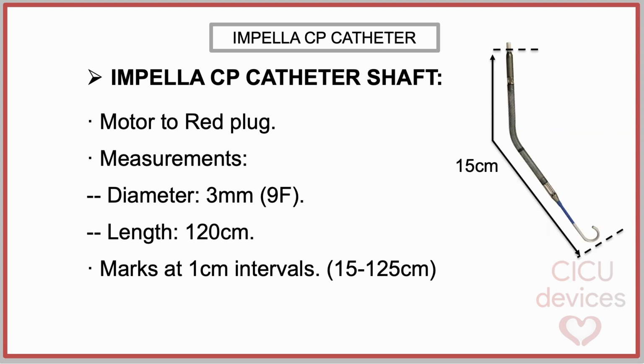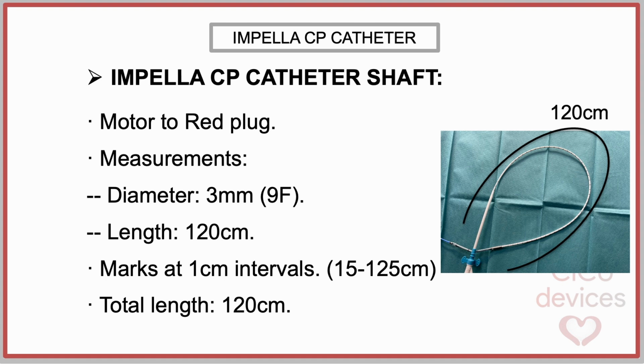Interestingly, the markings start at 15 cm, which corresponds to the estimated distance from the most distal end of the curved pigtail to the end of the motor. The last marking is 125 cm, followed by an additional 10 cm segment without transverse markings. In this way, we can establish that the catheter shaft actually measures 120 cm.